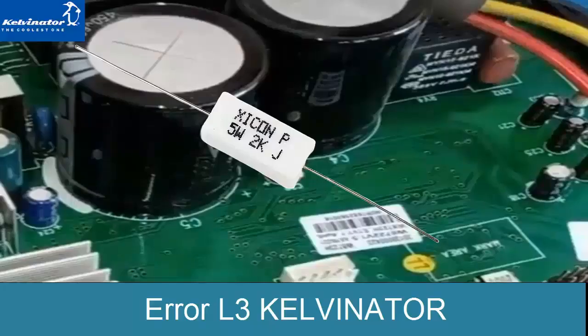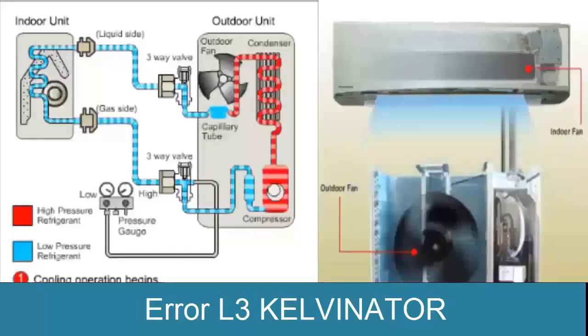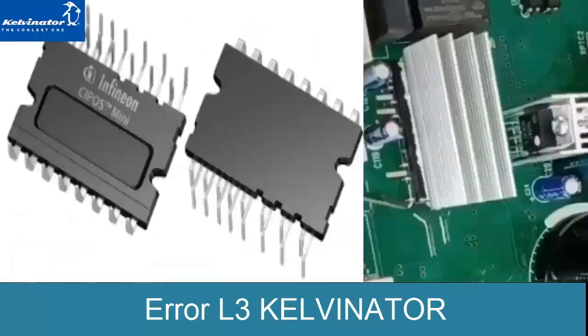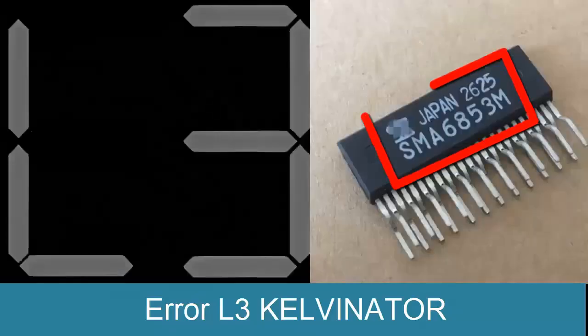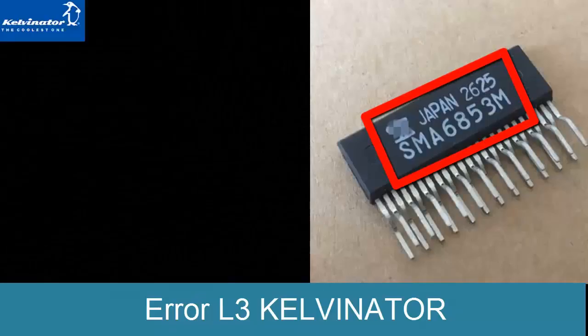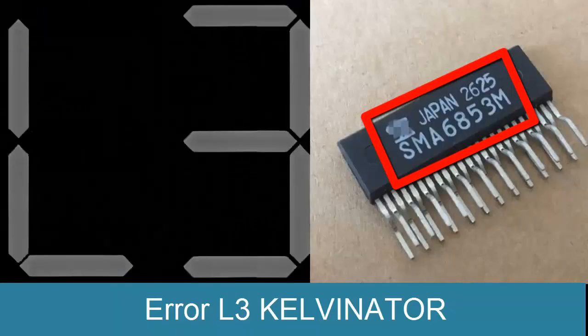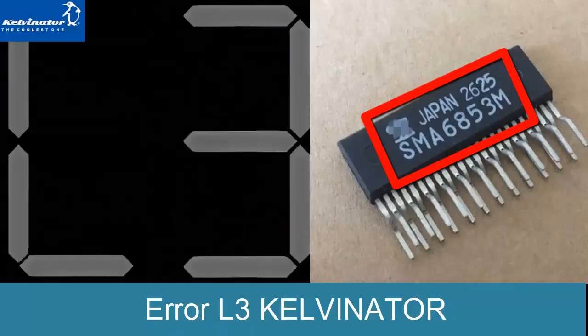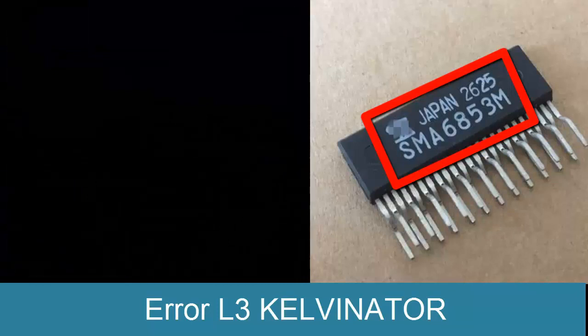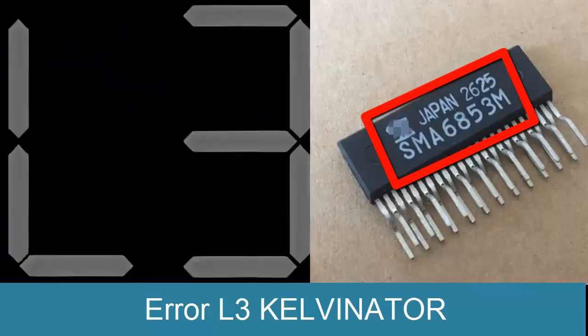Step 7: Ensure that the IPM output pins have continuity with the connector where the outdoor unit's fan is connected. Step 8: With the electronic board powered on, check the voltage present in the IPM electronic integrated circuit. To do this, use a multimeter set to direct or continuous voltage. Compare the corresponding pins, checking the datasheet or serial number of the IPM integrated circuit.